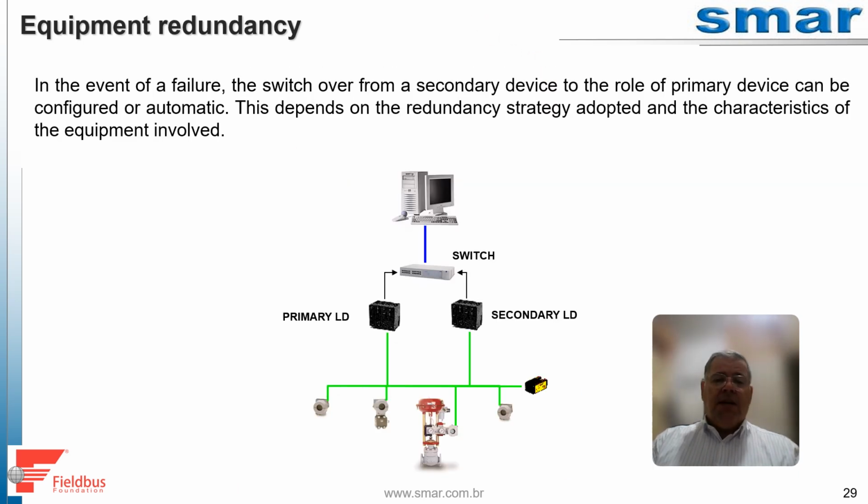In another case of redundancy, we can achieve redundancy for the equipment, controller, and link device. We have our primary device along with a secondary device as backup, and we can configure the secondary device to take over in case of primary device failure. It takes on the link device network duties. Then automatically the function can change from one device to another device.